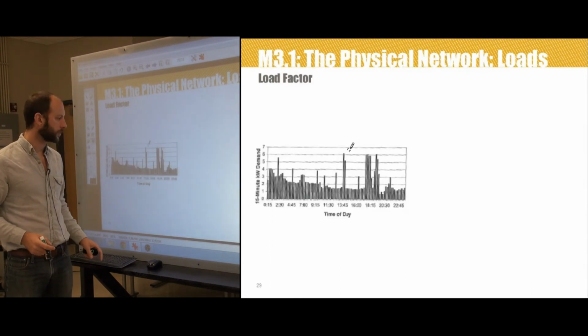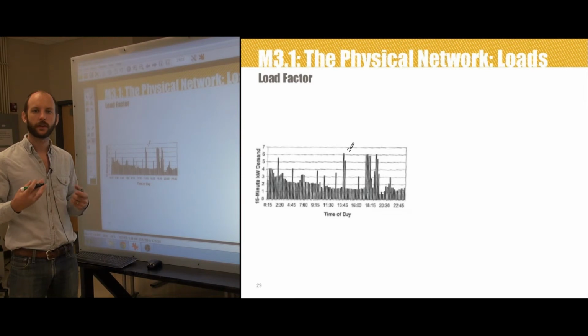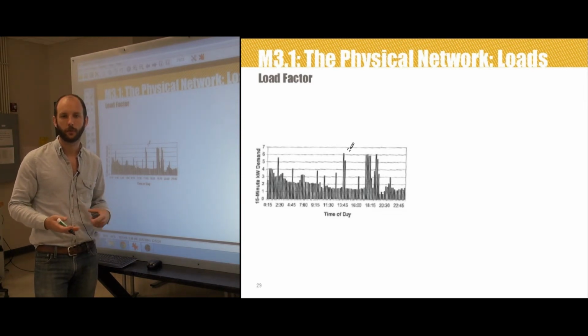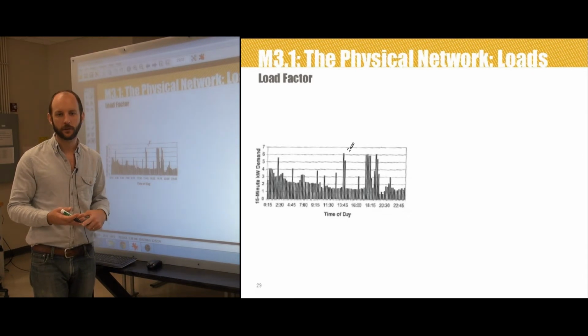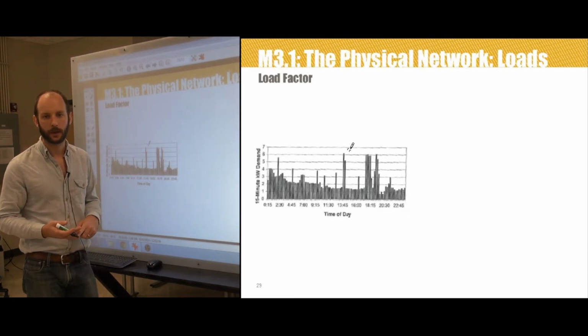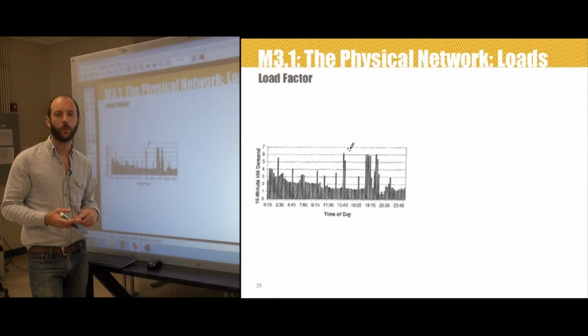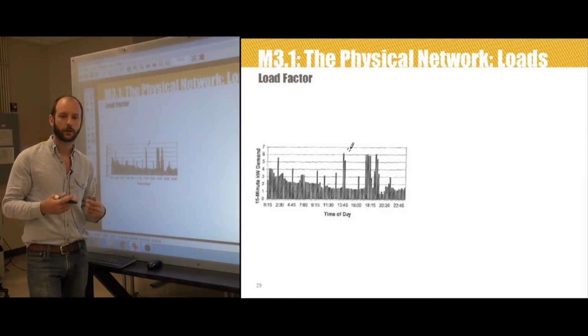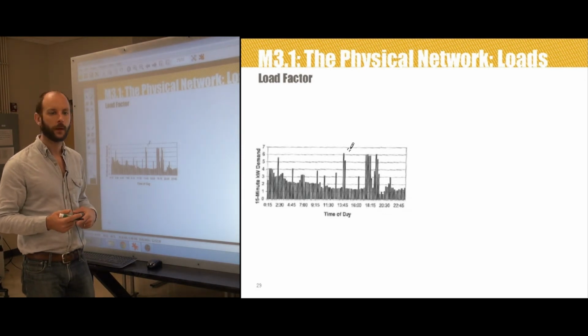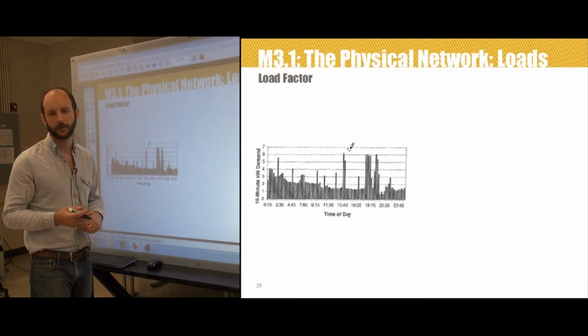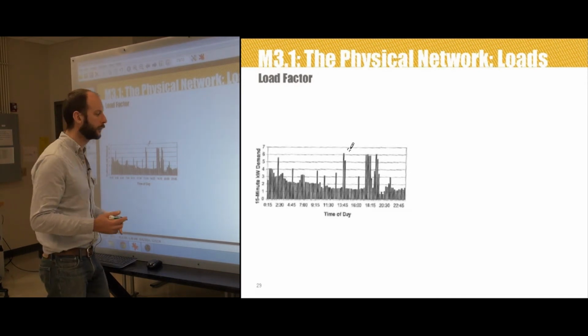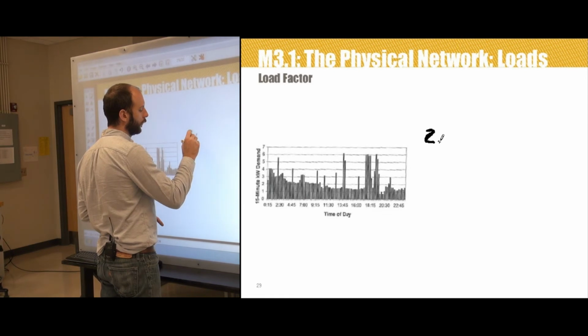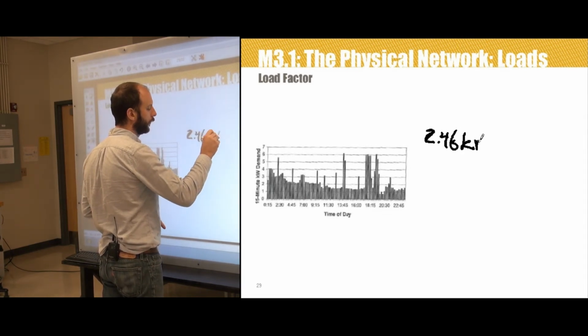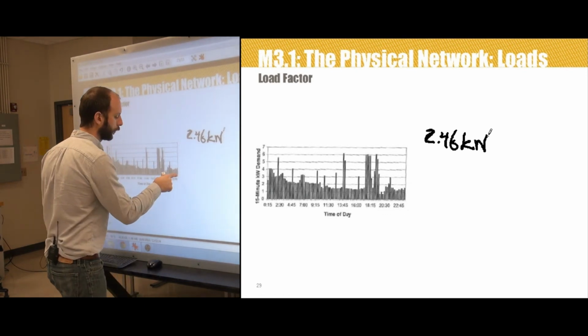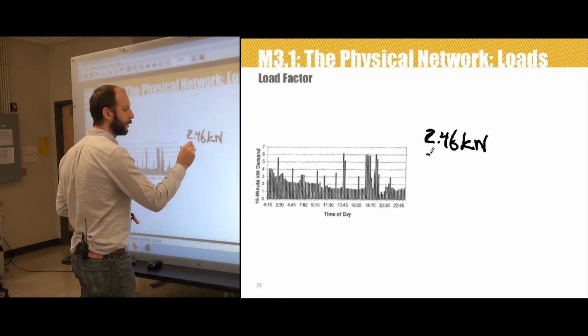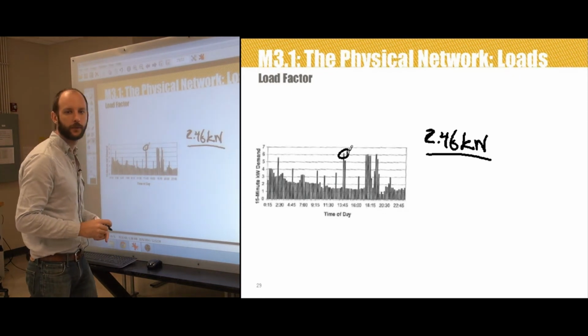Primarily the reason we do this is we're trying to calculate what's called load factor. It's a term that is used to describe the variability in a customer's load profile. And it's defined as the ratio of the average demand to the maximum 15-minute demand. And really what it does is it gives an idea of how well the utility's facilities are being utilized. Clearly, an optimal load factor would be 1. And how we calculate it is we just take the average 15-minute kilowatt demand and we divide it by the max. So before we did 2.46 kilowatts. That was the average demand, right? We summed all this up over the course of the day, divided by 24. And then we divide it by the peak excursion, which remember we show is that. So 6.18.